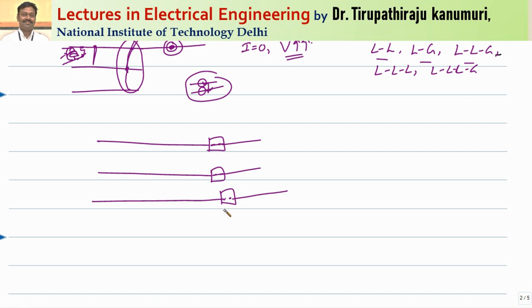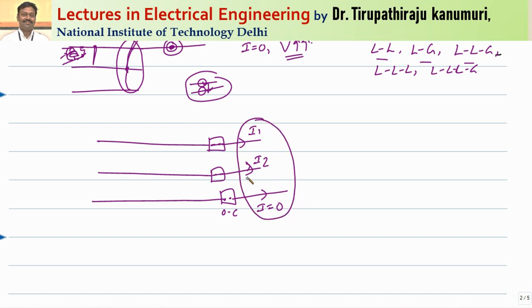Current I1 will pass in one phase and I2 in another, but in the third the current becomes zero. Because of this, imbalance comes in the current. Whenever unbalanced current comes due to open circuit — meaning only some phases are open-circuited, not all — this leads to unbalanced currents. This unbalanced loading of a three-phase circuit, if star-connected, leads to the circulation of negative sequence currents.